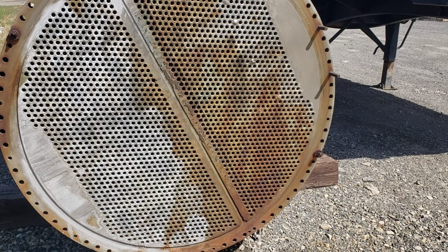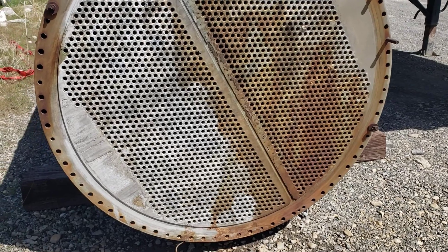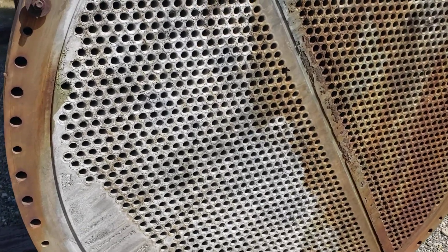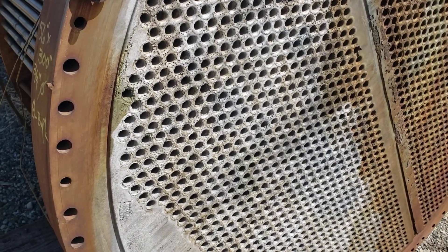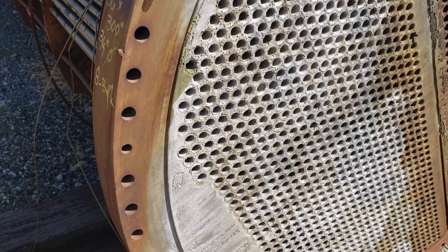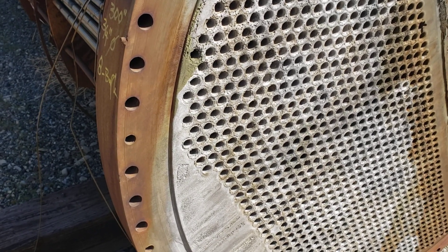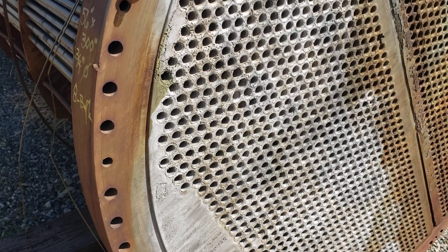Gentlemen and ladies, I thought I'd bring you along to show you an inspection of a heat exchanger bundle. This is a U-tube bundle. Its particular sizes are not that unique — it's a 56-inch diameter bundle, 300 inches long.